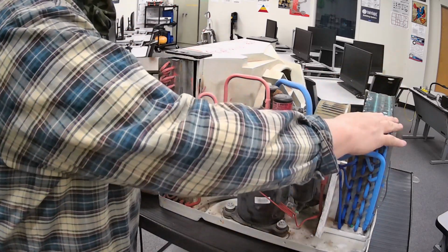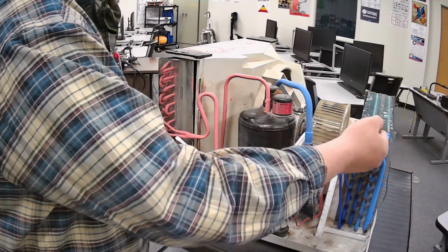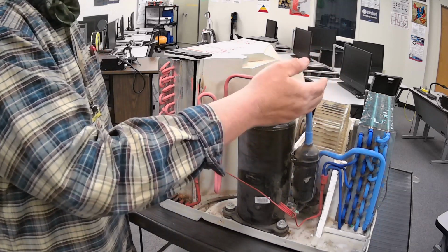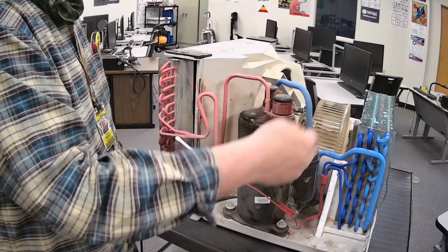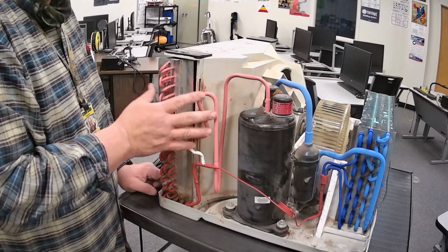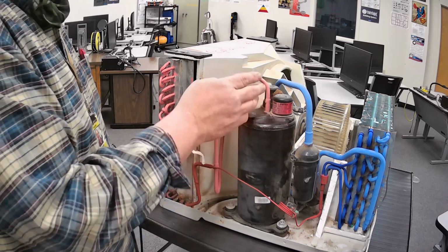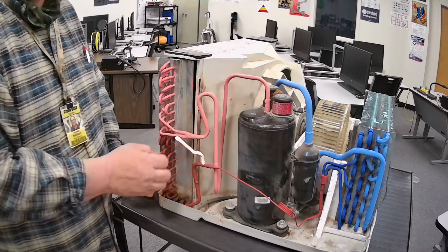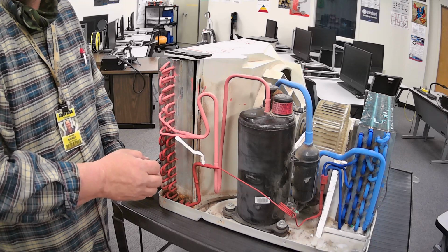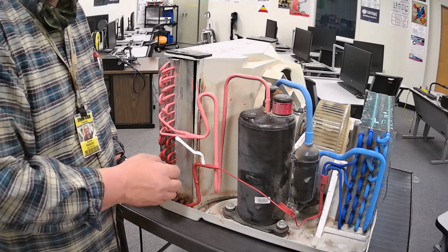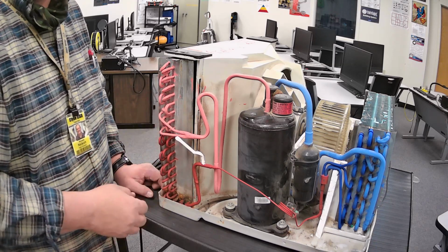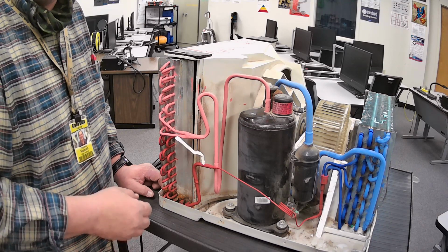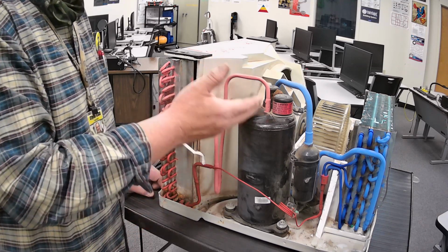We're trying to catch it inside and take it outside. So we make this a low temperature, and we bring the high temperature across it. We catch it. Now the refrigerant has the high temperature. I'm taking it through here, but we need to make it where we can eject it. So what we do is we compress it, make it 210 degrees. So 210 degrees is higher than the outside temperature, because if the ambient temperature is ever 210 degrees, we're dead. You follow me? So they make it well above the outside temperature.